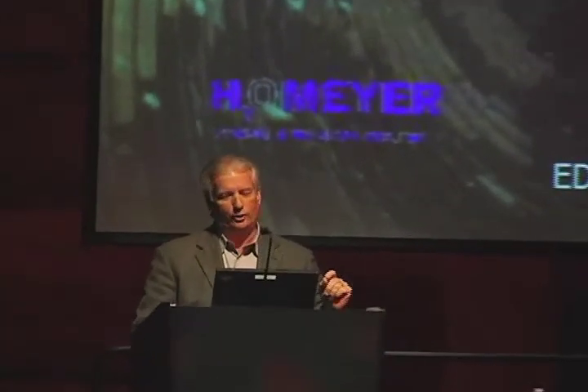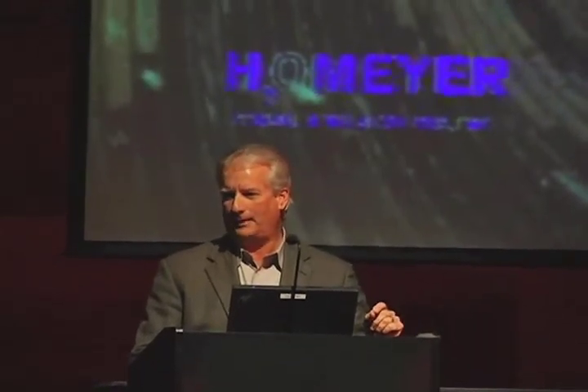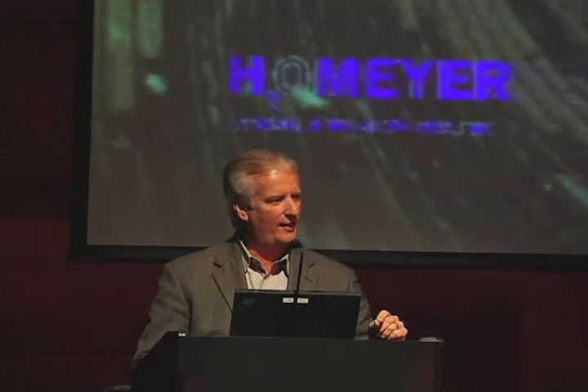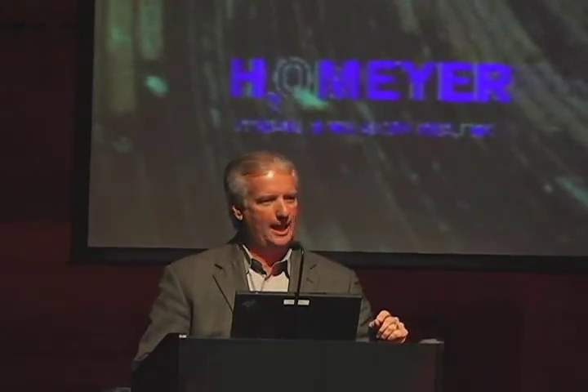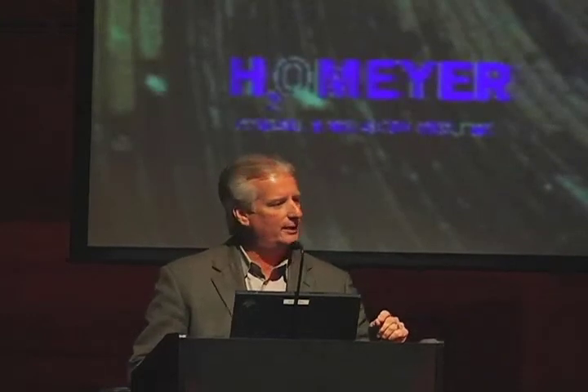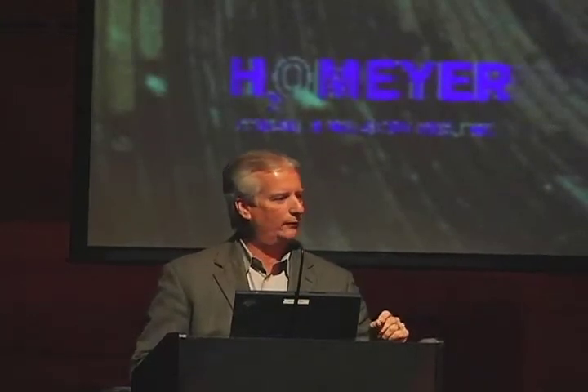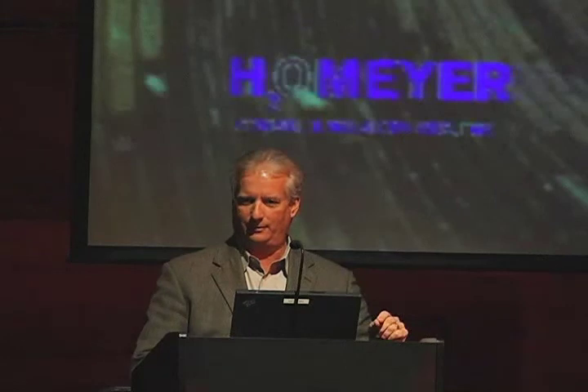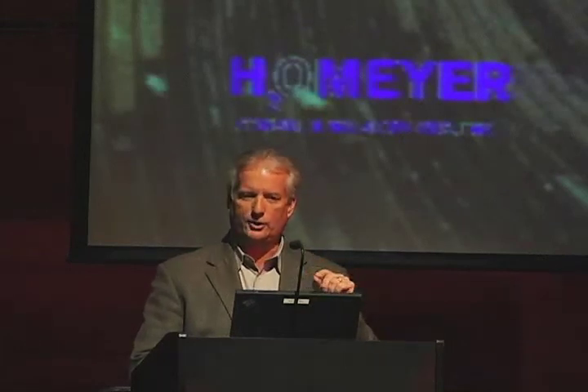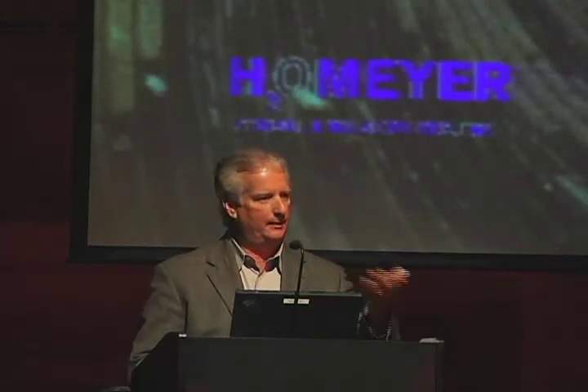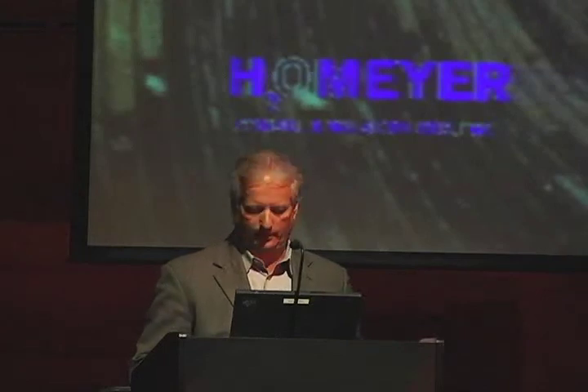These tubes are 25 thousandths of an inch thick. I don't know if you can visualize that. 25 thousandths of an inch thick. You don't have a lot of room to work with. They normally condemn a tube when it's 50% loss. That's 12 and a half thousandths of an inch. So the tolerance levels are very, very small, and they do that on purpose because the heat transfer efficiency is so great on that.